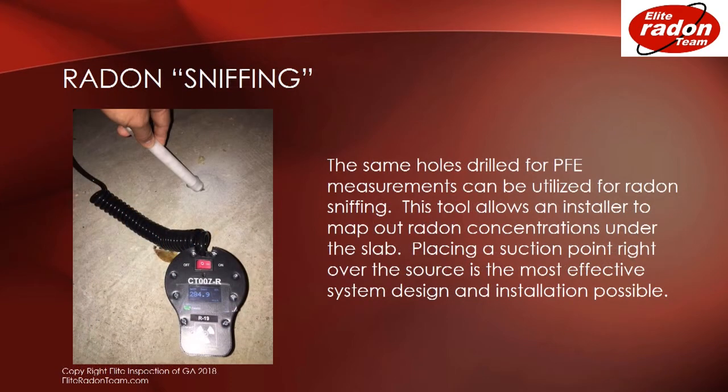The same holes drilled for PFE measurements can be utilized for radon sniffing. This tool allows an installer to map out radon concentrations under the slab. Placing a suction point right over the source is the most effective system design and installation possible.